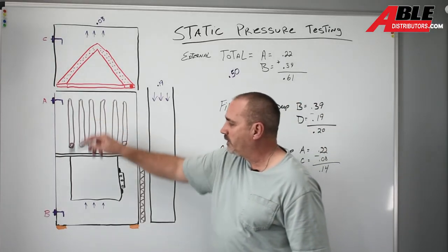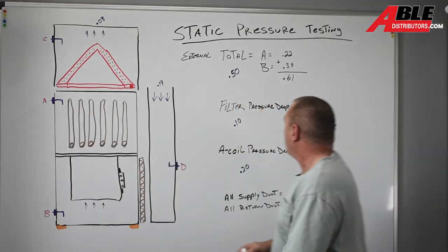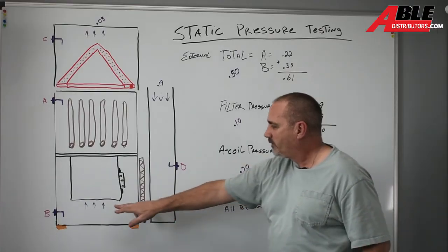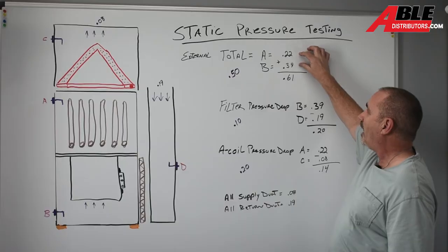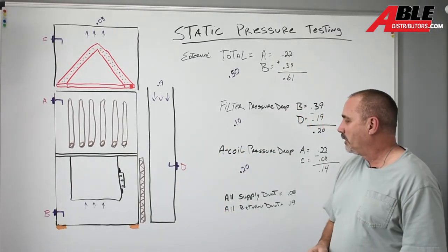So when you do these numbers, you can instantly tell where to look. Instantly with this being a 0.22 and this one being a 0.39, I knew the issues were going to be on the return. It's the higher number, it's an easy way to go.